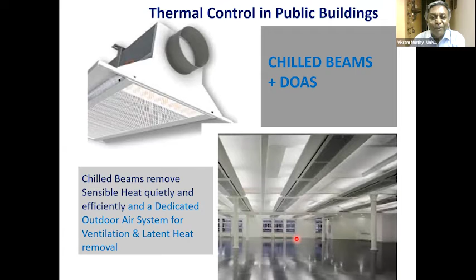The adsorption, ADSOR, chiller is made by Bryair. Debashish is from a sister company, but this is a wonderful device. Debashish is going to speak later today. It's a wonderful device which uses desiccant and vapor pressure difference to cool water down to 7 degrees, same temperature as a chiller, but it doesn't require electrical energy. It requires warm water at 36 degrees centigrade, not hot, warm water. You can easily get this warm water as waste heat, or using solar thermal, not solar electric, solar thermal, to get warm water. And they are making machines up to 300-400 tons.